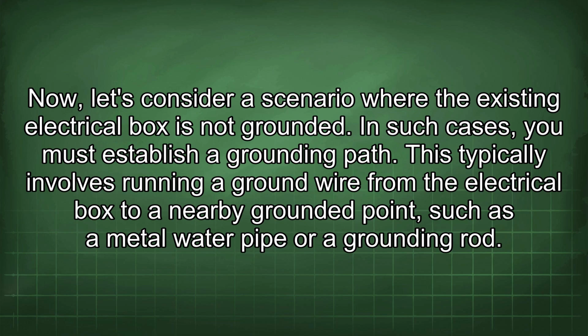Now let's consider a scenario where the existing electrical box is not grounded. In such cases, you must establish a grounding path. This typically involves running a ground wire from the electrical box to a nearby grounded point, such as a metal water pipe or a grounding rod.